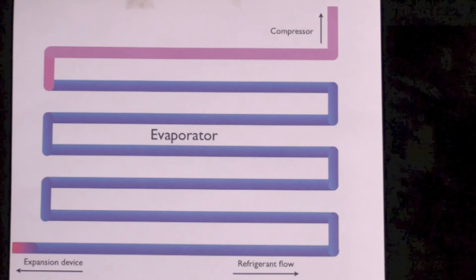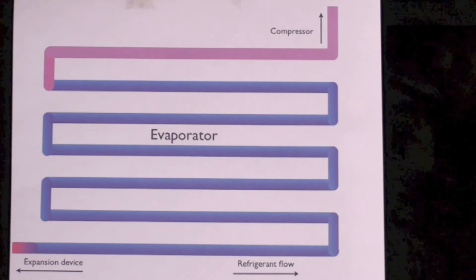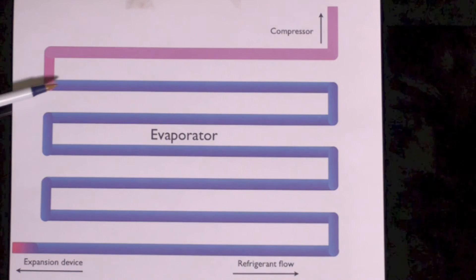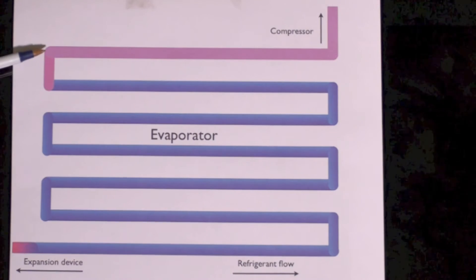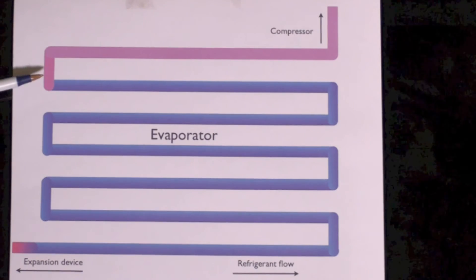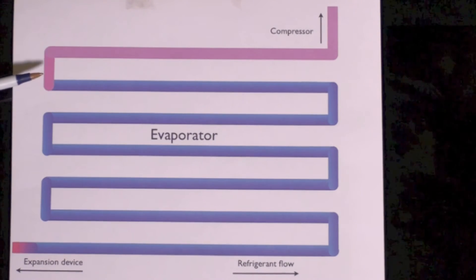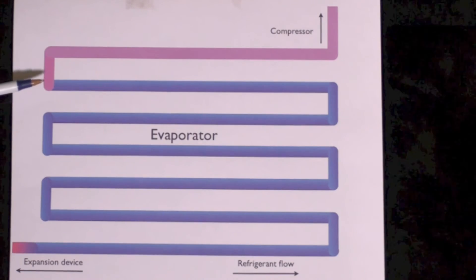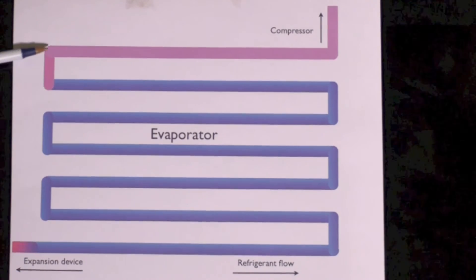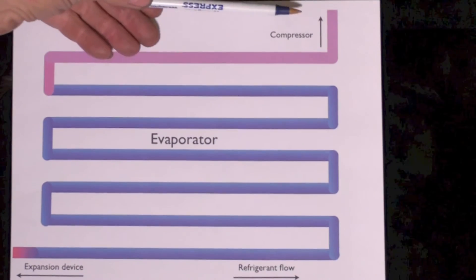Out towards the end of the evaporator, you see the color difference here. We have run out of liquid. There's no more liquid left, and we have gas going up to the compressor.